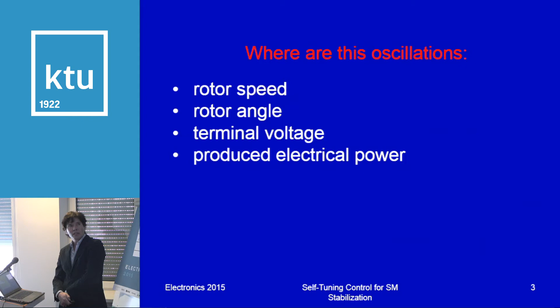It is funny, but it is true: even when both inputs are constant, the variables of synchronous generators oscillate. We can see these oscillations in the rotor movement, so rotor speed and rotor angle oscillate, and also in the stator voltage and in the produced electrical power. Here are the results of measurements on a real power plant. This is a synchronous generator with 30 megavolt ampere nominal power.